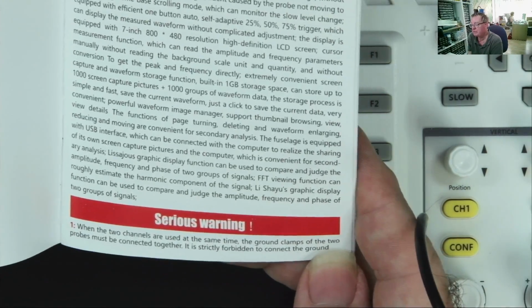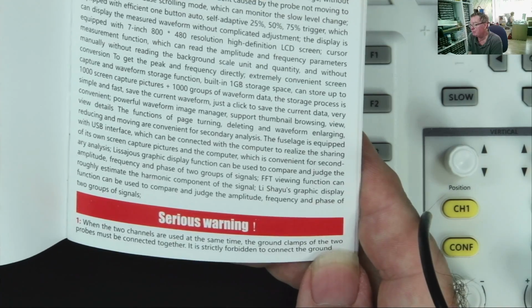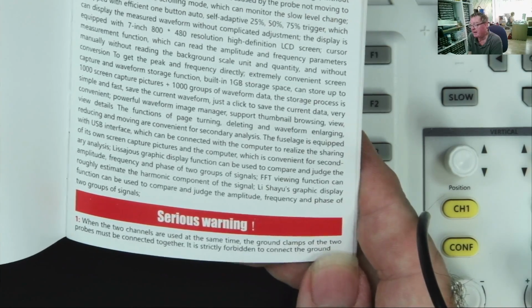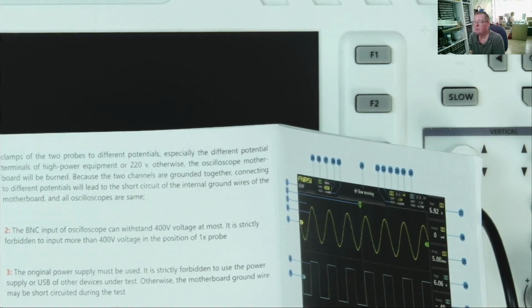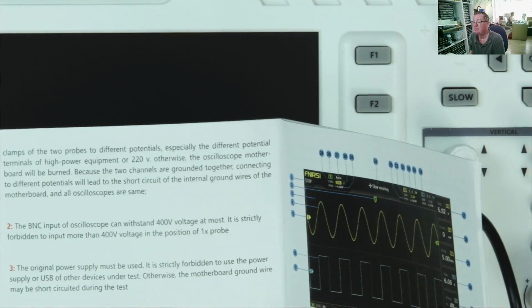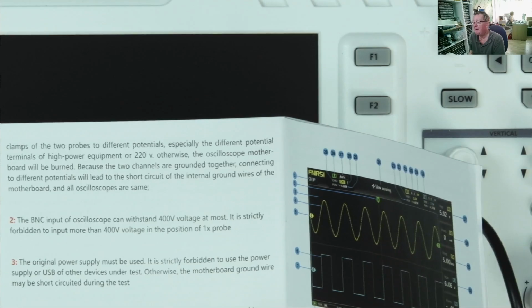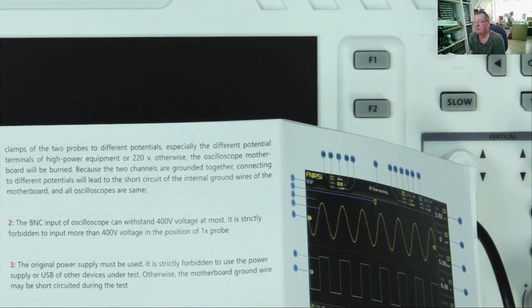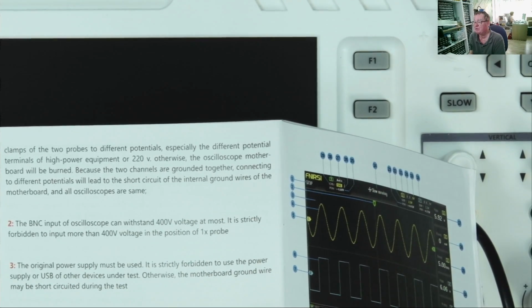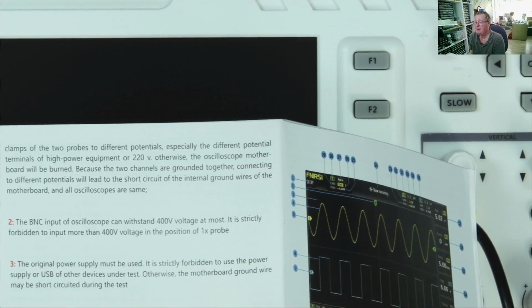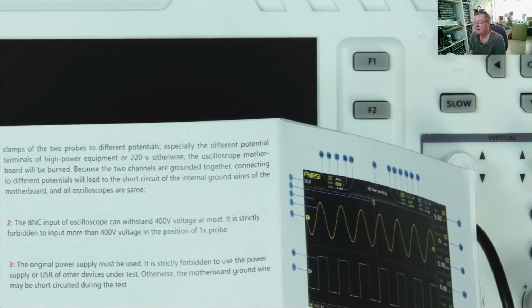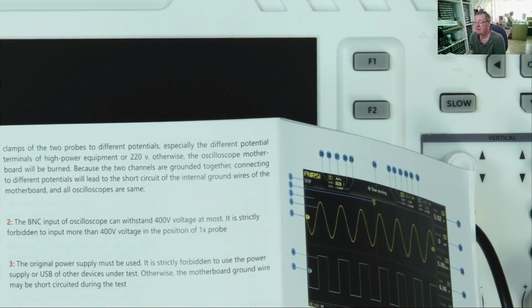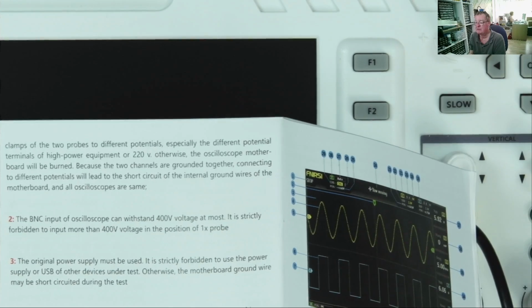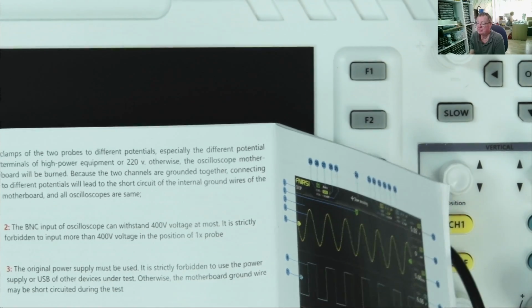When the two channels are used at the same time, the ground clamps of the two probes must be connected together. It's strictly forbidden to connect the ground clamps of the two probes to different potentials. This is very normal, especially the different potential terminals of high-powered equipment. Otherwise, the oscilloscope motherboard will be burnt. Because the two channels are grounded together, connecting to different potentials will lead to a short circuit of the internal ground wires of the motherboard. All oscilloscopes are the same.